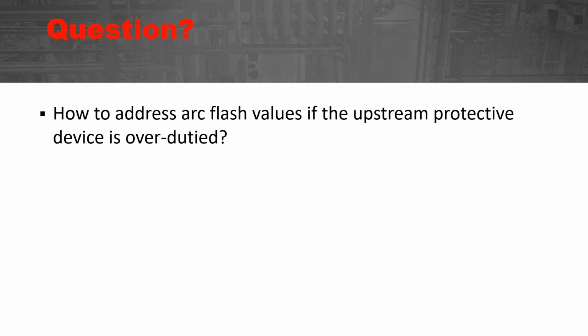You can also install what's called a triggered current limiter, which is basically a high-speed fuse that switches in a fuse, which interrupts the fault in a quarter to half cycle, which significantly reduces the arc flash values down from, like, say, category 4 to a category 2. If it's a low voltage, like 480 and below, if you use one of those devices, it's basically category 1.